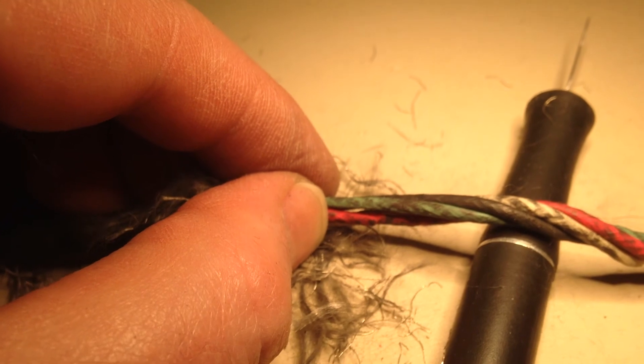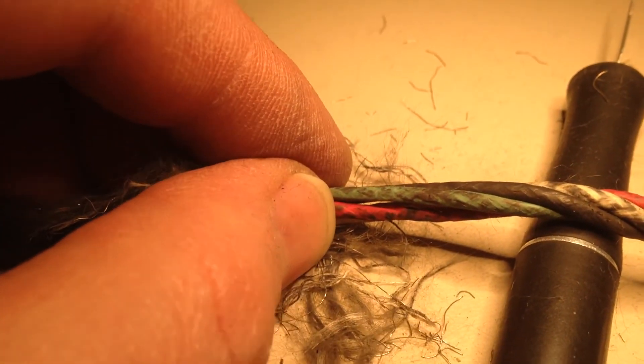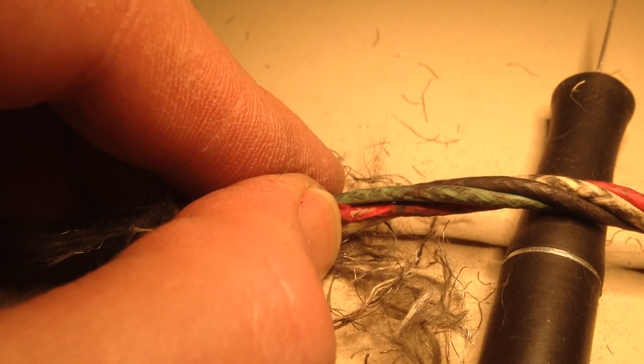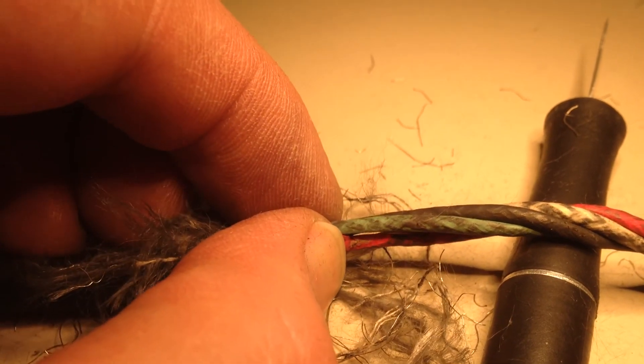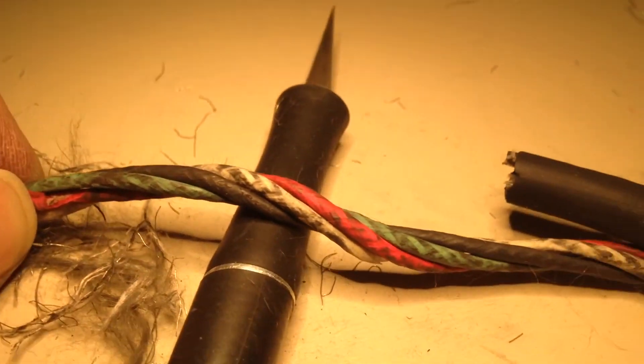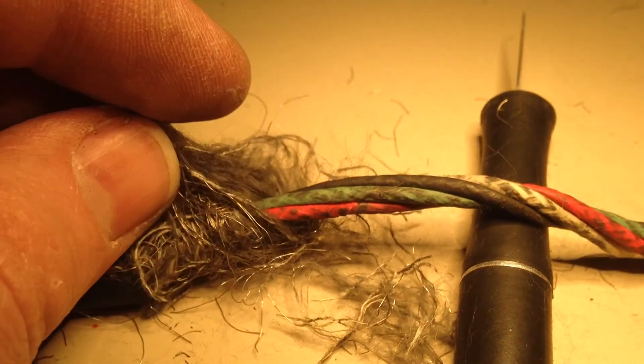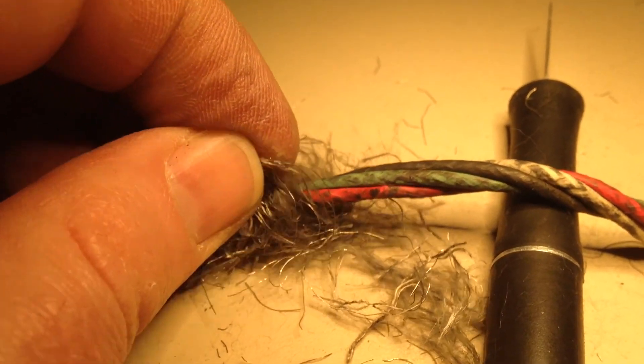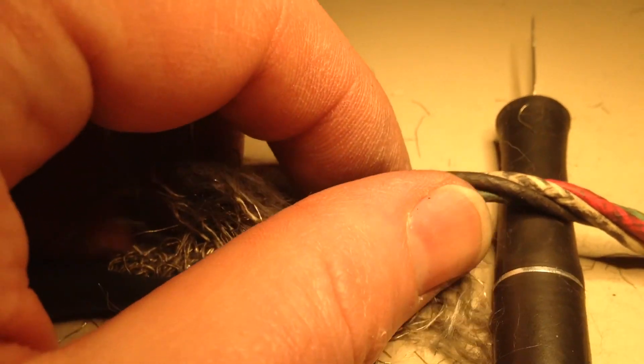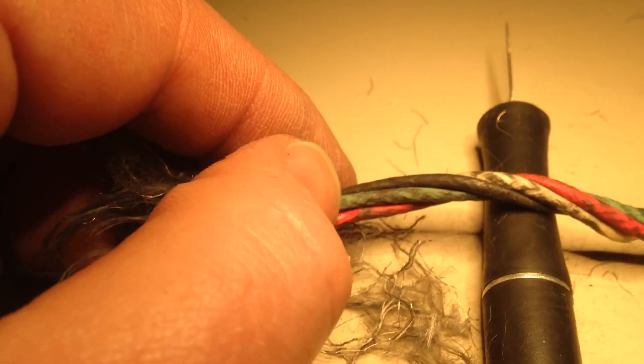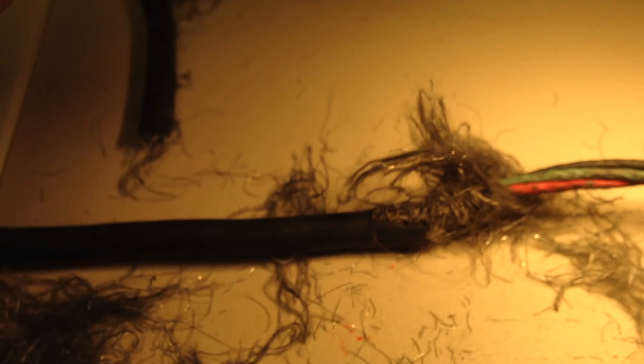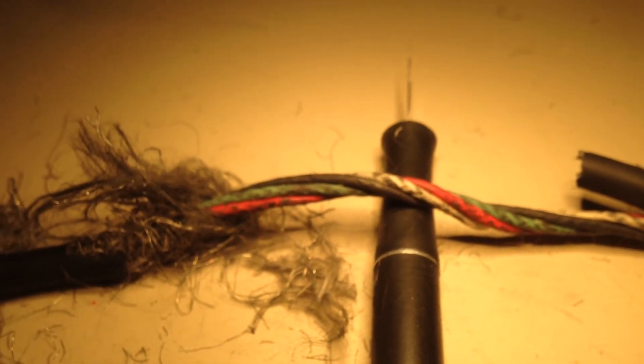And I find the fault in this wire. If you look at the red wire, the insulation is peeling back right here and exposing the inner conductor. And there's another section on the white wire back here where it's also peeling away. What I think was happening, this was shorting against the stainless steel braid right here and causing that intermittent short. So I'm going to go ahead and cut this section out right here and let's see if that fixes the issue.